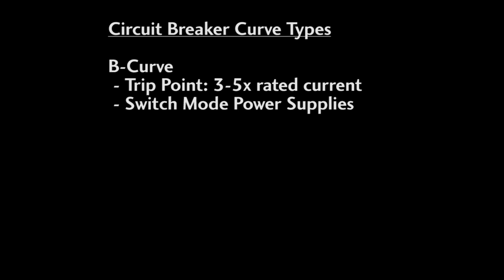Circuit breakers are rated using a curve type. A B curve type circuit breaker can handle 3 to 5 times the rated current before it trips. They are great for small switch mode power supplies where you need to be able to handle the inrush current but need to be in a couple amp range while operating.